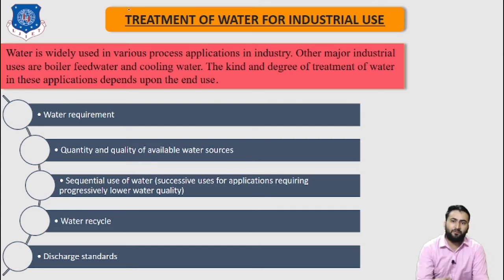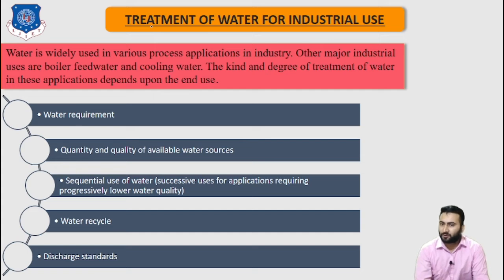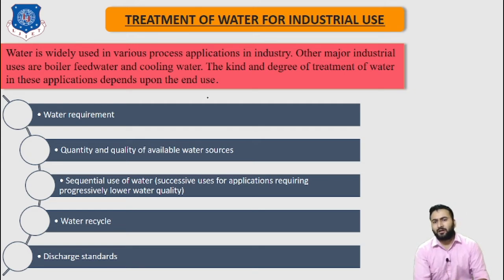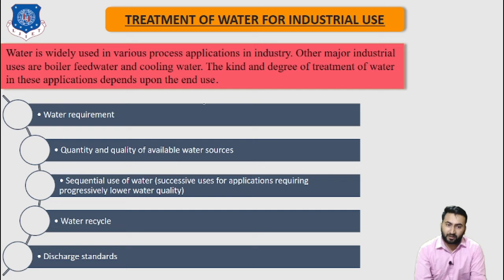Normally, if we need water for cooling purposes, we need to only remove corrosive material. But for boiler feed water, we need to remove scale formation, and water used in food processing must be free from bacteria and toxic substances. Improper treatment of water for industrial use can cause problems such as corrosion, scale formation, reduced heat transfer in heat exchangers, reduced water flow, and product contamination. These effects can reduce equipment performance or cause equipment failure, increasing energy costs and pumping costs.